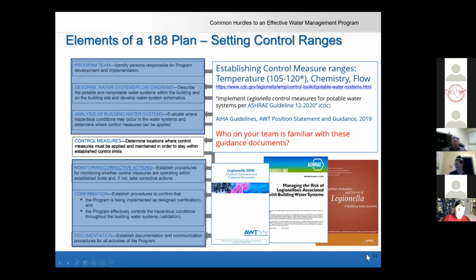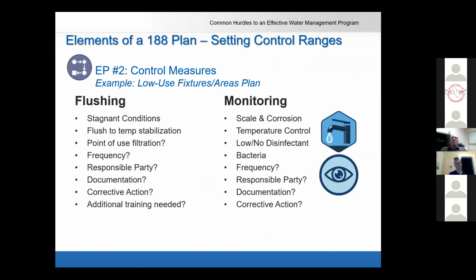Next slide, Christy. Yeah. So here's an example, just setting the control range for low use fixtures. Let's say we've got an EVS closet or a shell space where we've got patient rooms that are not in use yet. Those are essentially potentially dead legs. So how do we do it? We've got potential stagnant conditions. We can use flushing to reduce the stagnancy and flush to temperature stabilization on some sort of schedule, right? And then we could use point of use filtration, as you just mentioned, but how frequently do we do it? Who's the responsible party and how do we document it? And what is our corrective action to take? Do we need additional training? Is this something EVS is going to do, or is this something plant ops is going to do?